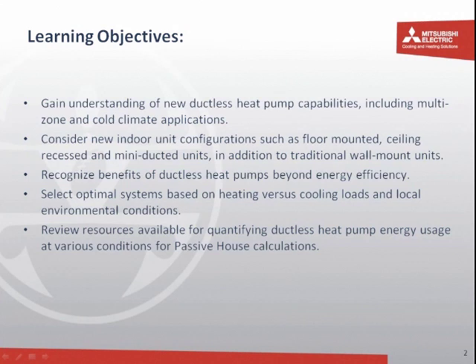We're going to recognize benefits of ductless heat pumps that go well beyond just their energy efficiency, especially in a super tight home, the ability to have actively managed airflow and easily accessed filtration components add some significant indoor comfort and indoor air quality benefits. We're going to talk about selecting optimal systems depending on where your project is. That may be based on the heating load, maybe based on the cooling load, maybe based on the latent load, the amount of dehumidification that you need to do. But in all cases, the mini split offers the opportunity to select a system that's perfectly matched to your needs.